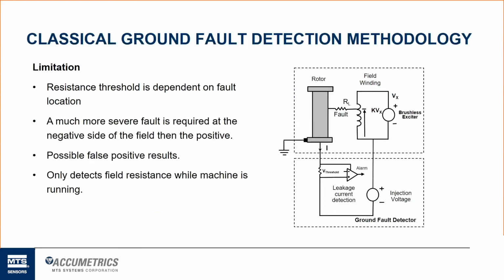So the classical ground fault detection method, as I was talking about before, is a DC injection voltage that they put out onto the exciter shaft itself, and that biases the negative side of the field slightly higher than rotor ground. It looks for that current leakage to go from the field windings to rotor ground. Then there's some circuitry with a threshold set to measure; if you have current and you have voltage, you can calculate using Ohm's law what the field resistance will be. If the resistance drops below a certain threshold, it'll trigger the alarm. In most cases, as I mentioned earlier, that's a single point threshold set at 10K ohms.